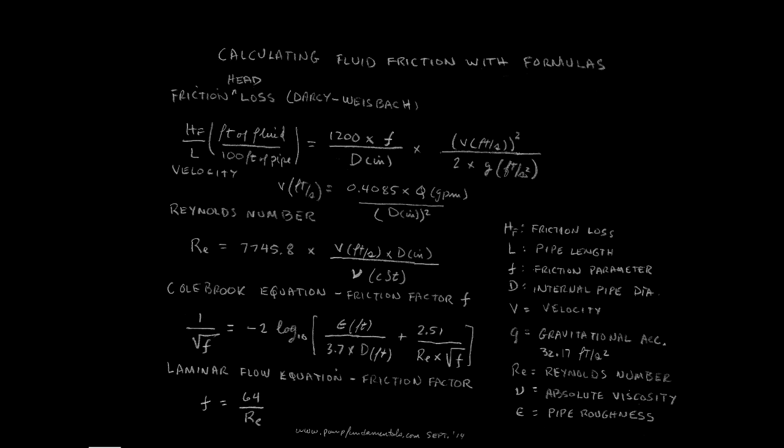The third one is the Colebrook equation, which is the heart of the matter. It tells us what the friction factor is depending on the roughness of the pipe, the Reynolds number, and the pipe diameter.